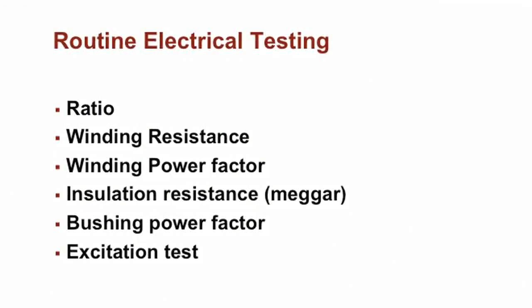Okay, and then you have routine electrical test results: ratio, winding, power factor. I talked about the insulation resistance. So this is putting 2 or 5 or 10 kV on the windings, and then also looking at what the insulation strength to ground is, of the windings or the core to ground, and bushing power factors and excitation tests.